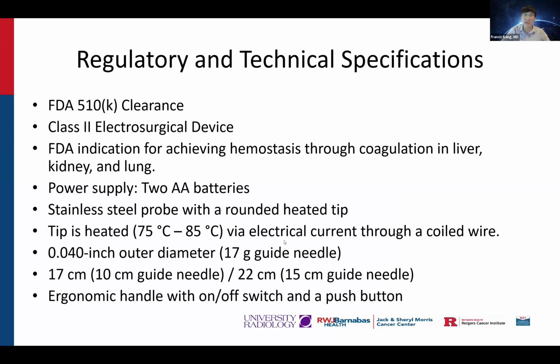It is a stainless steel distal probe with a rounded heated tip that is connected to the handle to cauterize targeted areas of tissue. The tip is heated to 75 to 85 degrees via electrical current through a coiled wire. The temperature of the distal tip is controlled with a thermistor, while the temperature of the tip is distributed with a thermal conductive epoxy. It is a 0.040 inch outer diameter, which is compatible with a 17 gauge guide needle. It is available in two models, K10 and K15.